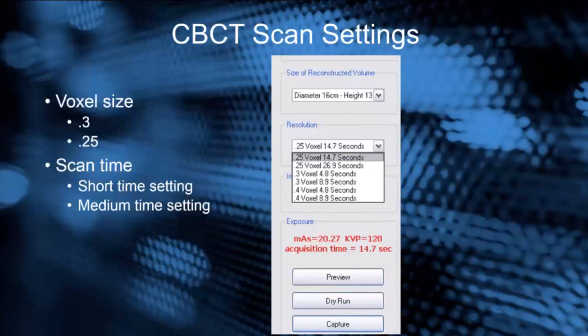For cone beam scan settings, you don't necessarily need a high-resolution scan for airway studies. A voxel size of 0.3 or 0.25 should be sufficient. You can also use a short or medium scan time setting, depending on other things you want to know from the scan. For more information about scan time settings and image resolution, please visit one of my other videos.